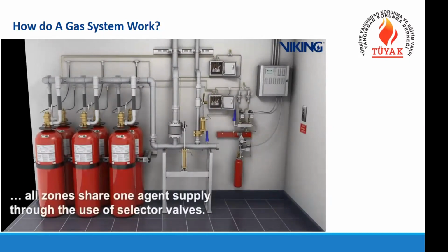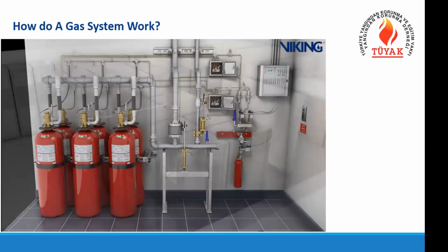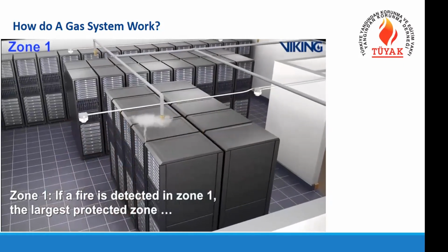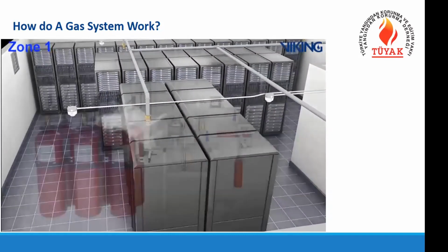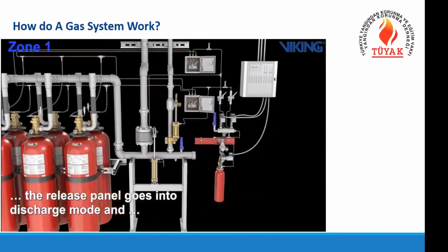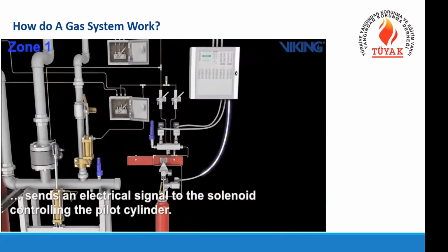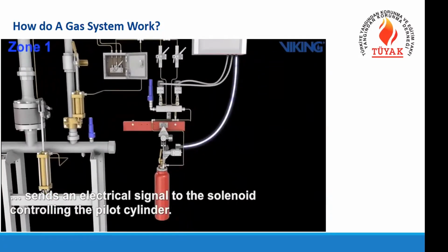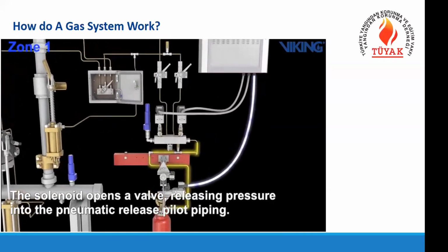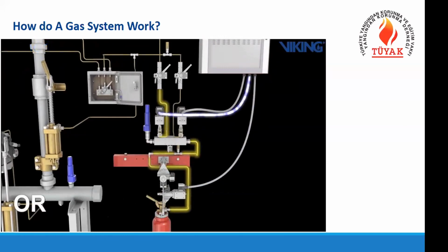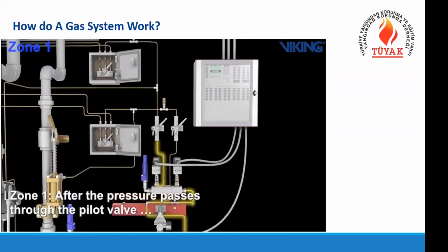So we have rooms with the extinguishing system fixed with pipes and directional valves, each servicing a single room. And when you see in the largest zone, we have detectors that detect the fire with smoke, and it sends a signal to the panel, and the signal is also used to actuate the pilot valve, which is operating the other valves in the system. And by knowing that the first zone has the fire, we are activating the first zone activation solenoid. Or if zone 2 is activated, then the zone 2 solenoid is activated. So the detectors will decide which zone should be activated.